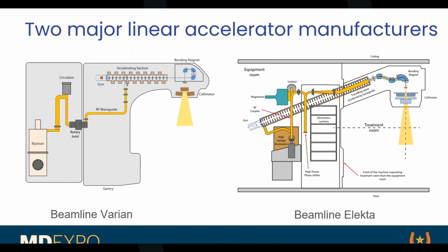Yeah, sure. Since we're at much higher kVp, the target is very different from a tube target. Absolutely, yes. If you come down to our booth, we actually have one that we can show you. It's a water cooled target, and tungsten is your typical material for targets because it's a high Z target. Often it'll have two materials. It'll have copper in there as well to do some filtration, so we get the right mean energy out of it. But the main difference is that the amount of power that goes into it is quite high. If we didn't have good water cooling around it, it would fail almost instantaneously. It would melt, which would not be a good thing. So it's smaller, and depending on the machine, some will have different targets for different energies, so we'll have maybe more than one.